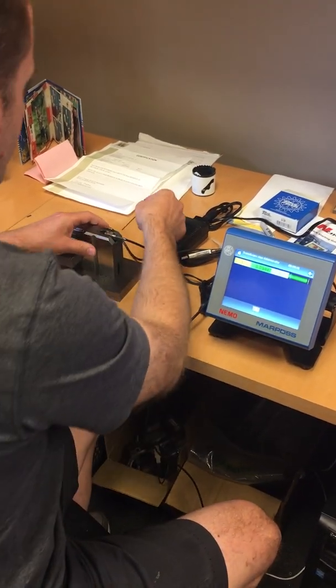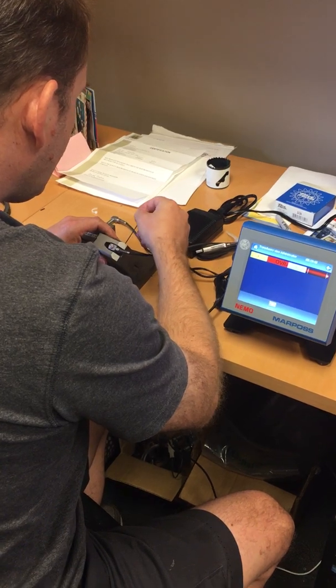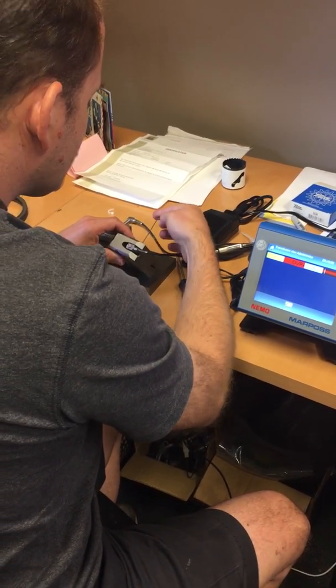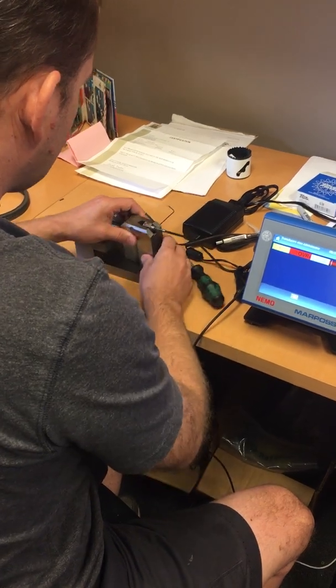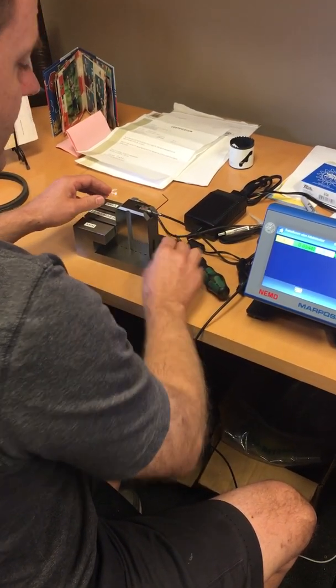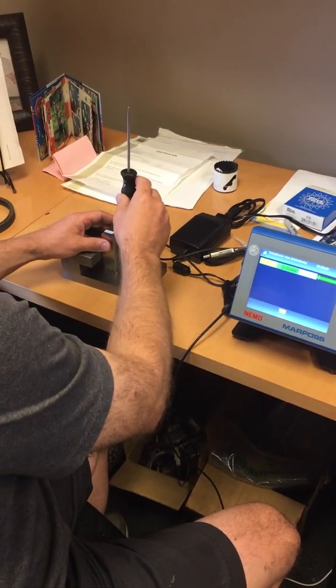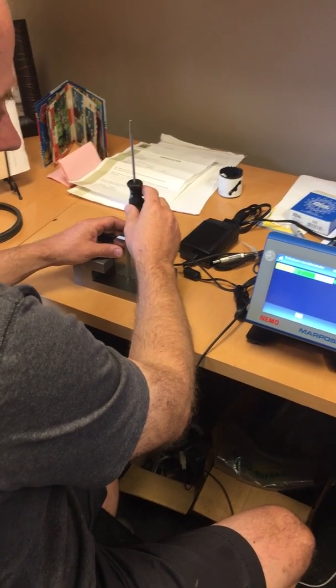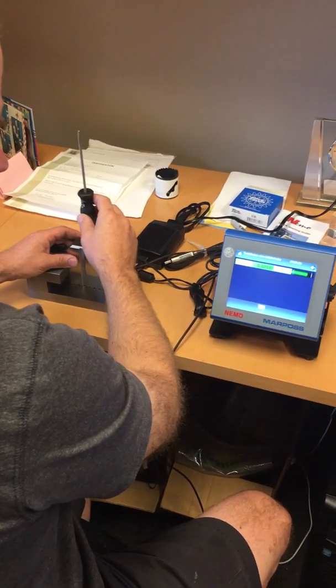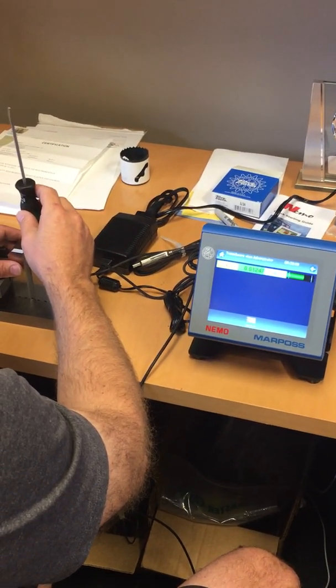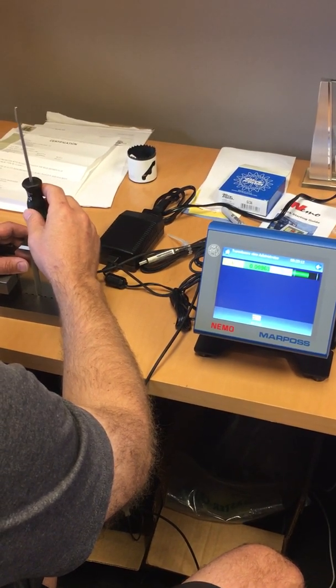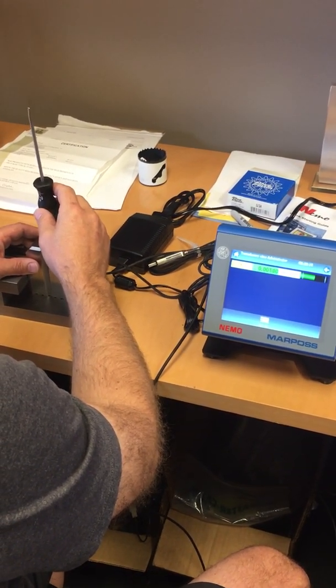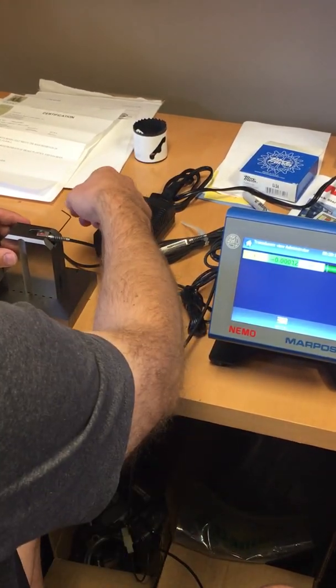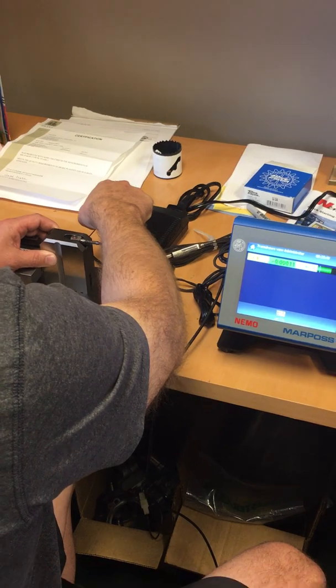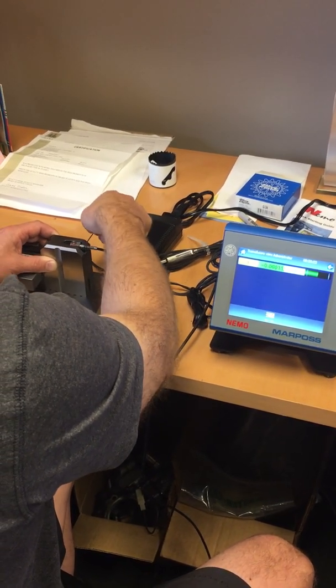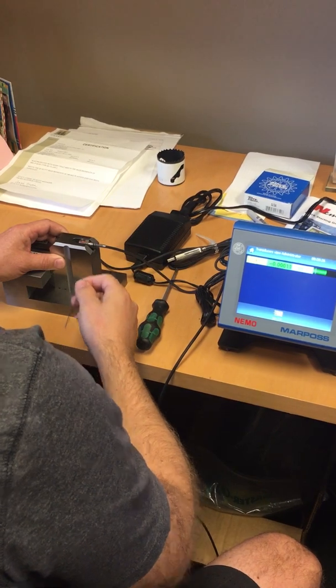Take your Allen key and just slightly snug up the Allen key to give the clamp a little bit of resistance. From here, just lightly tap the LVDT until it reads 0, or close to 0, plus or minus 2 thousandths. That's good. Go ahead and clamp the LVDT by tightening the set screw. Do not over tighten.